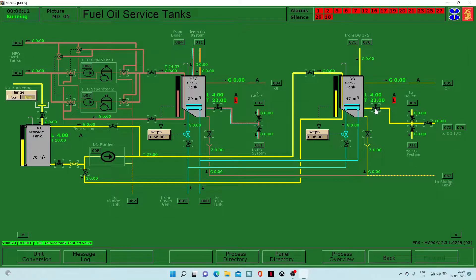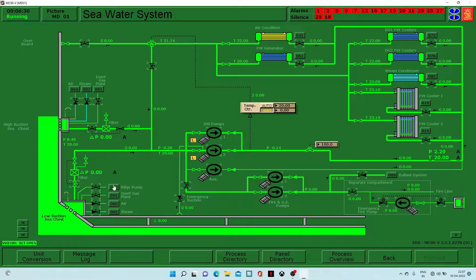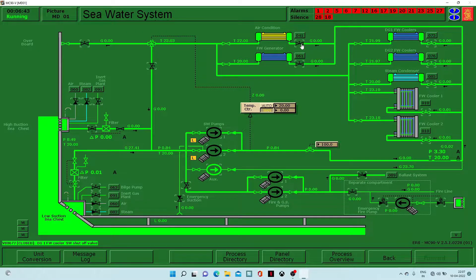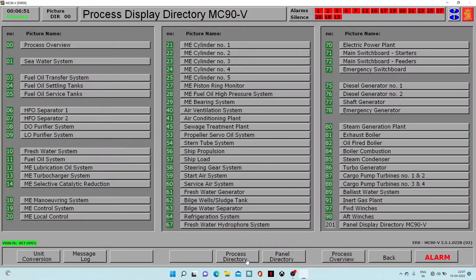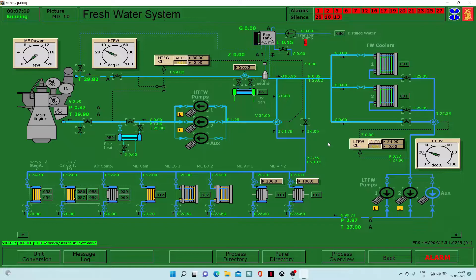We go to the process directory, then fuel oil service tanks. We have opened the valves for the service tank, but we haven't opened the valve from the service tank diesel oil supply, so we need to first open the quick closing valve and then open the non-return valve. Our sixth step is to go to the sea water system — open the valve for the low suction sea chest, turn on the auxiliary pump, and open all valves in that line. Then go to fresh water system, turn on the pump, and open all the valves.